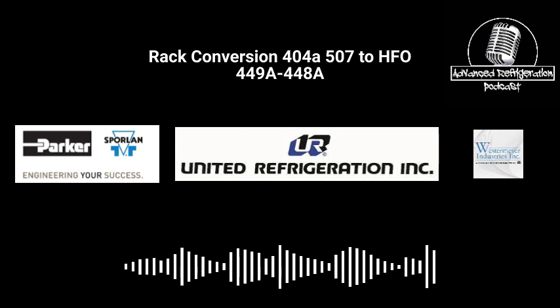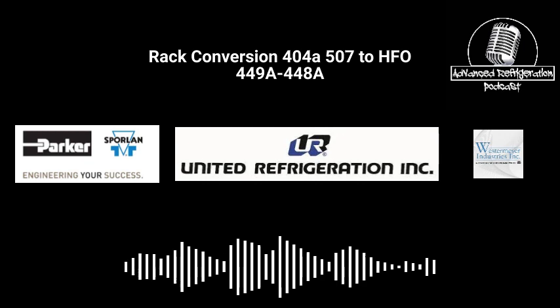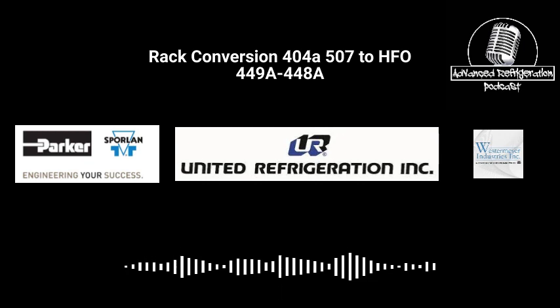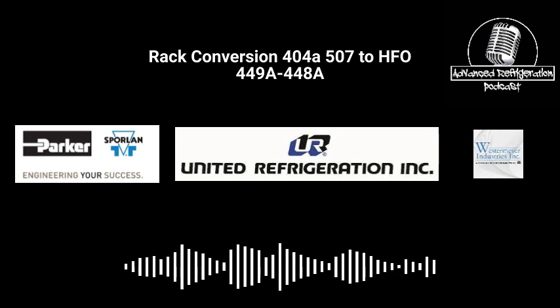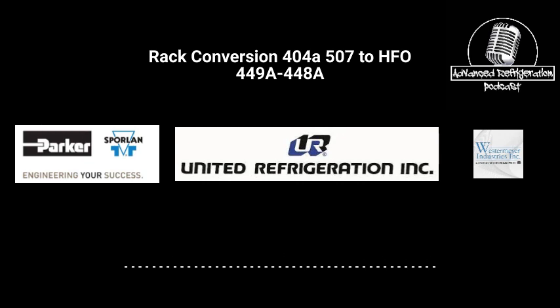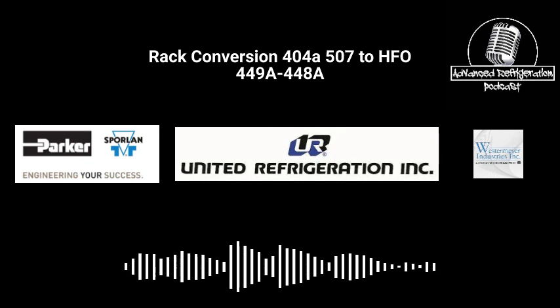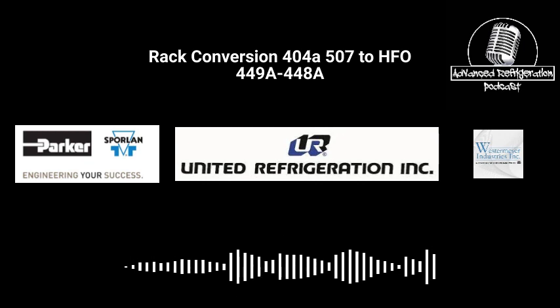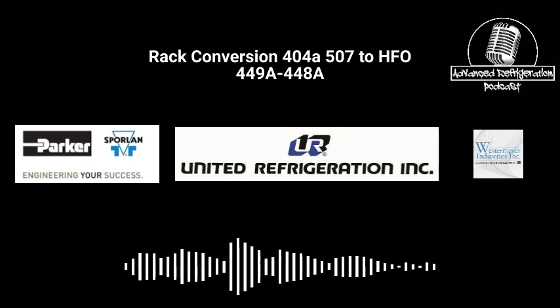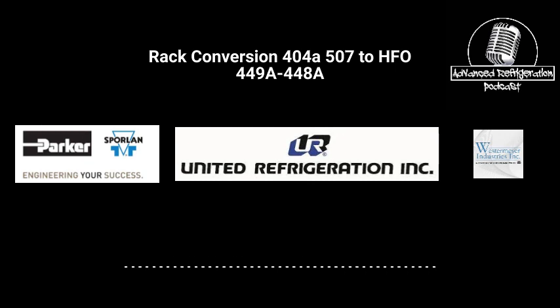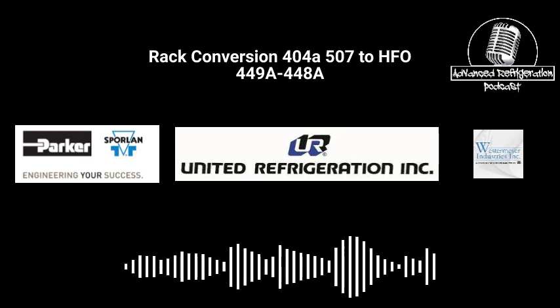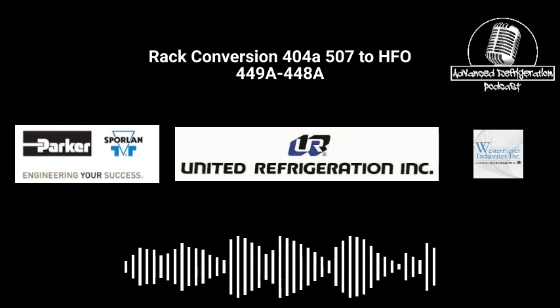It can shut itself off in case the compression ratio gets too crazy. There's a lot of cool little nuances you can do with that controller. Yeah, I've never seen it with the pressure transducers, just the bare bones with digital unloading. But when you get those out, if you're on a startup, you need to program them. They're not pre-programmed, and I've never seen an OEM program one yet, so be aware of that. It's super easy, you just tell it how many unloaders it has.